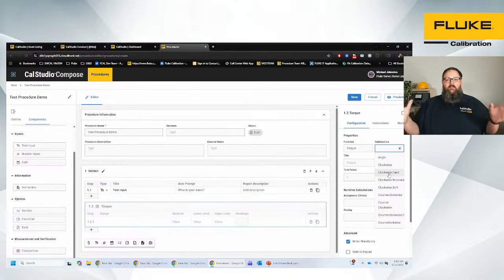Without all of that overhead that comes in with those types of events, where I recall personally going through an issue with a tolerance scope option, and I had to look at all of the things that calibrator had touched over the past year, and many of them did not use the scope option at all, but there was no differentiation in the system of which parts of that standard were used. That's really where this allows us to dig deeper than we really ever have before, where we're linking these together at a parameter and function level.